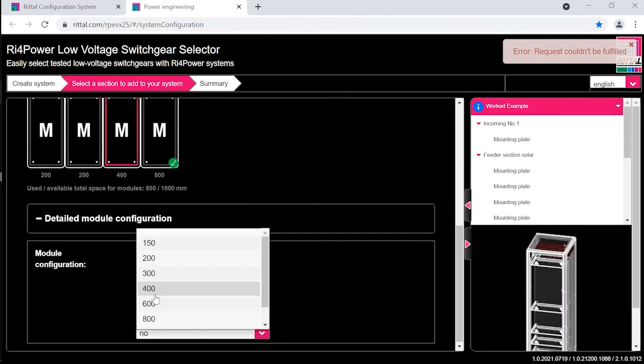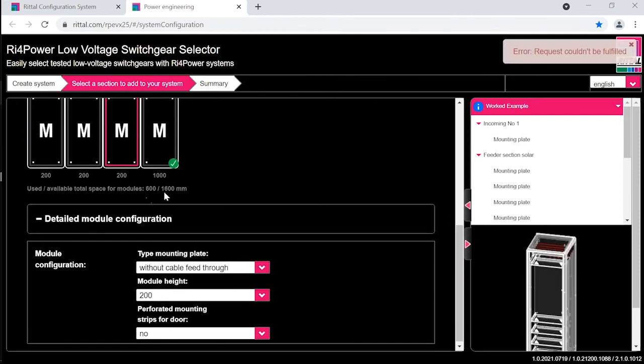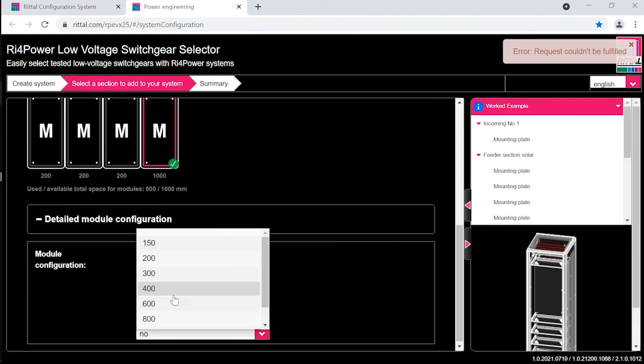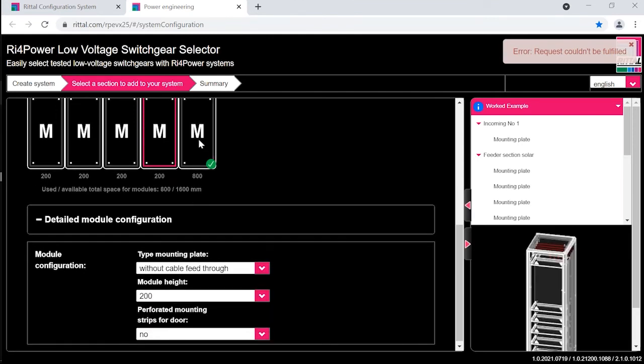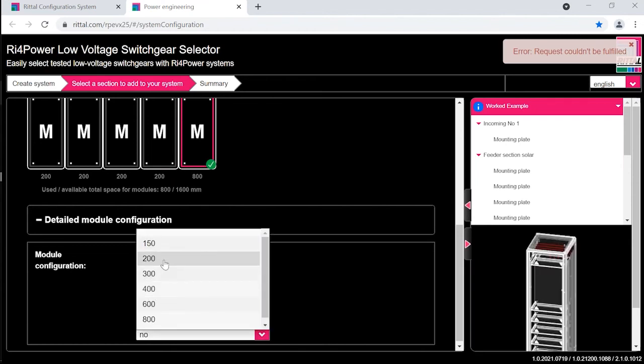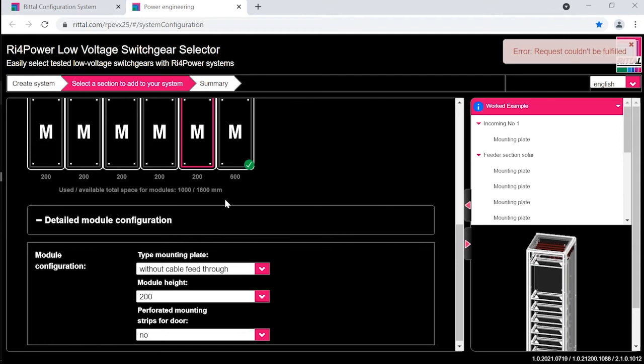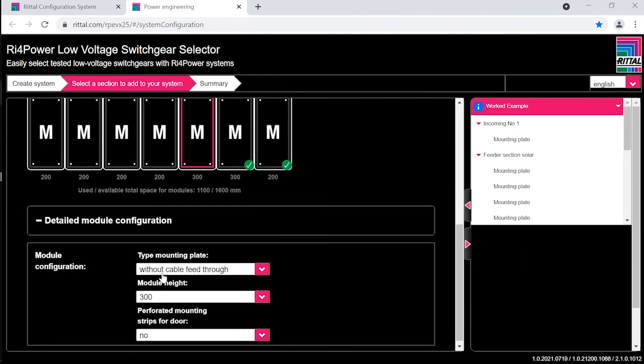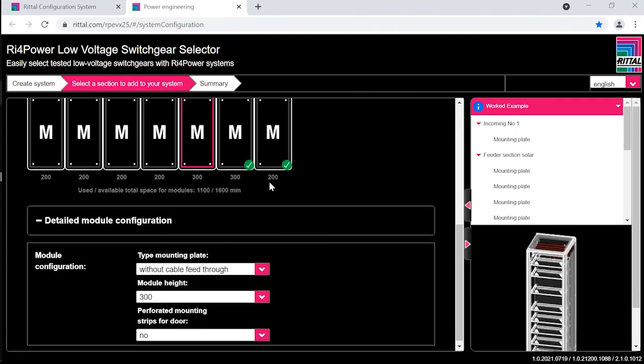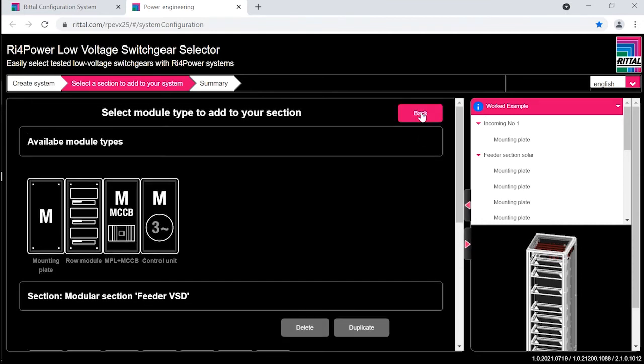So while we're doing this, behind the scenes, the software is accumulating all the information for the bill of materials and the drawings. But being online, it's very fast acting, and you can change this at any time, change the door sizes, the widths. So you don't have to go back to the beginning. You can physically go back one page, and that is a big improvement over our previous software system. So now I've changed this around slightly. We have 1, 2, 3, 4, 5 200 high compartments for the circuit breakers, and 2 400 amp circuit breakers behind the 300mm high compartments. So that looks good.